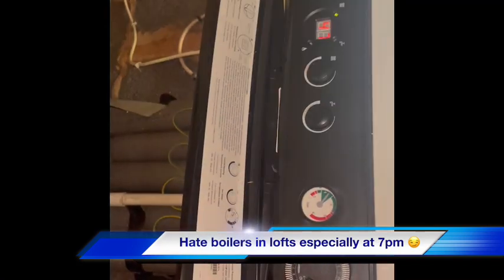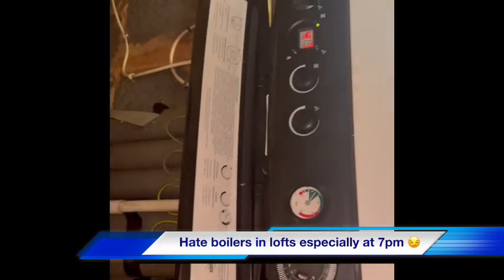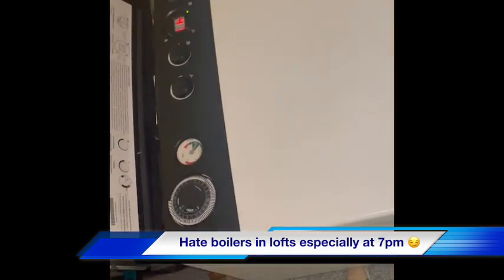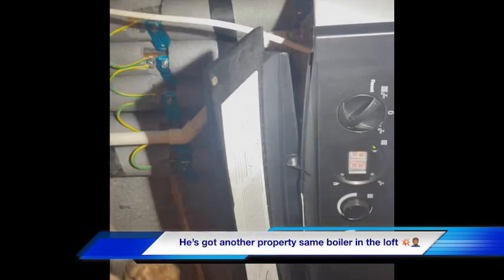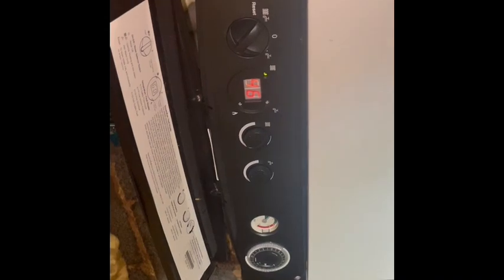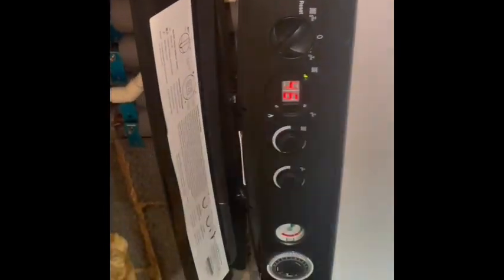We've got a Potterton Gold 28 HE. Some of the radiators aren't heating up properly. I came out to this probably about four months ago because the pressure release valve was dripping, so we recharged the expansion vessel and checked the PRV operation, and that's been fine since.